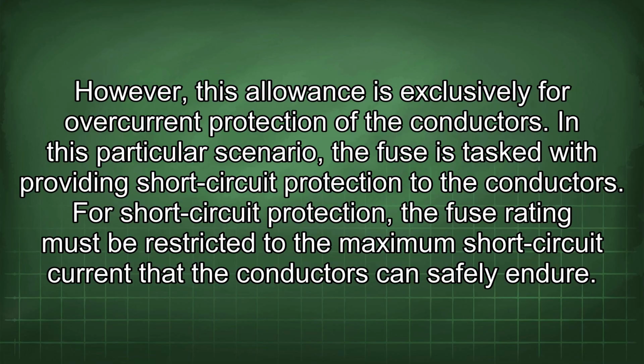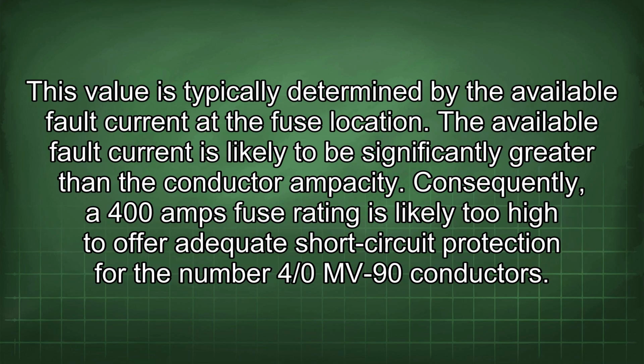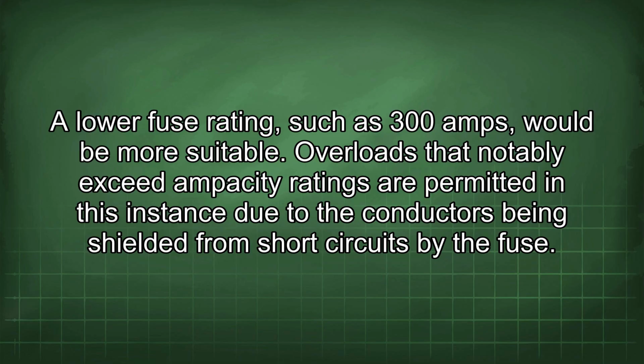In this particular scenario, the fuse is tasked with providing short-circuit protection to the conductors. For short-circuit protection, the fuse rating must be restricted to the maximum short-circuit current that the conductors can safely endure. This value is typically determined by the available fault current at the fuse location. The available fault current is likely to be significantly greater than the conductor ampacity. Consequently, a 400 amps fuse rating is likely too high to offer adequate short-circuit protection for the number 4/0 MV-90 conductors. A lower fuse rating, such as 300 amps, would be more suitable.